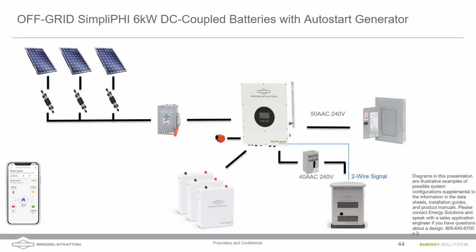I have a trivia question. We've got about 6 minutes left, and Kenny asked a great question. It's in the Q&A. He asks a question about what was his original state of charge before charging his system, and he provides some information here. He has 2 5 batteries, right? And he's charging at 22 amps. He does this for 5 hours. He then charges in an absorb cycle at 2 amps for just 6 minutes. So he's got 150 amp hours and 2 5 batteries. He charged for 5 hours at 22 amps. Okay, so he's added 110 amp hours to a system that has a total of 150 amp hours. So everybody, what was his approximate state of charge when he began?